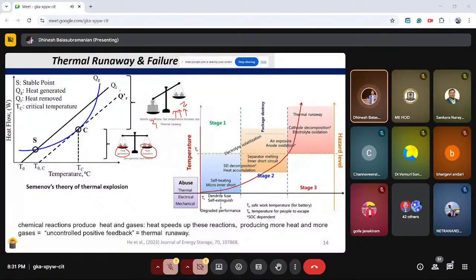The first curve talks about the heat removed plot, and QG is the heat generation plot; this is the stable point. This stable part is what you need to operate your system, and when you move away from this stable region, it results in a high temperature condition. The chemical reaction produces heat and gases due to the electrochemical process; the heat speeds up the reaction, producing further heat and more gases. Because of this, an uncontrolled positive feedback mechanism comes into picture, resulting in thermal runaway.